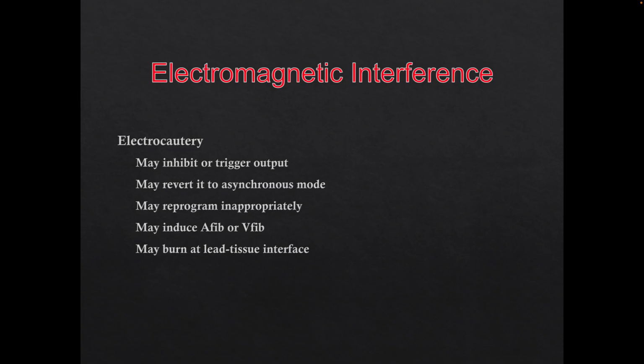Could have been that maybe they came up in that mode. And then what winds up happening, which is the correct mode to select? I don't remember if I go over all that too, but the correct mode to select depends on what the patient's doing. If you're having intermittent asystole, I would say just leave it in DDD mode because you don't know. And you can play around with the settings on this. You can play around with rate. You can play around with PR interval, or AV delay, we call it. You can play around with the sensitivity and the mA on this. So you can say I want DDD, but maybe it'll only atrial pace because you extended the delay long enough. We can do that obviously with these too. We can program a lot with these.